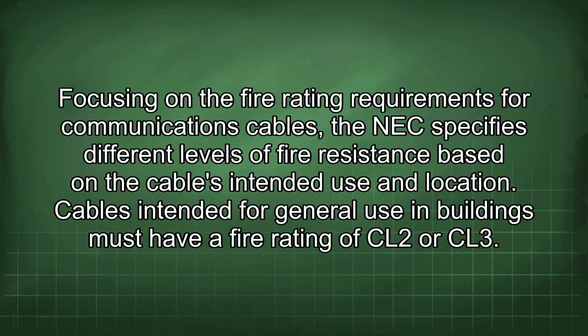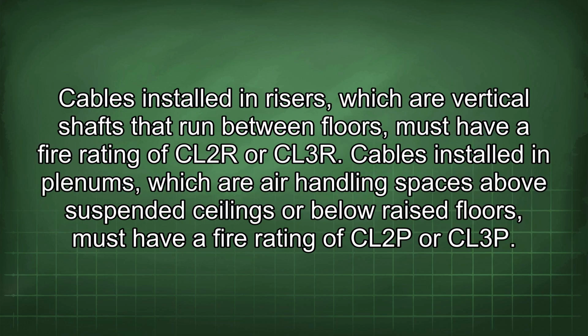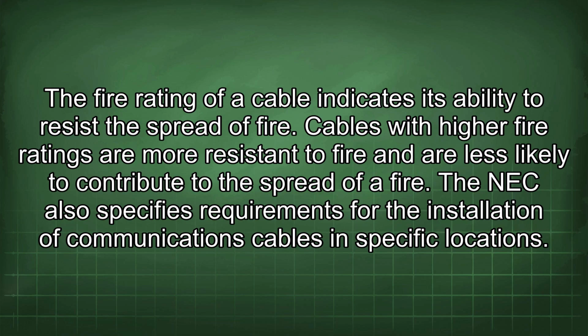Focusing on the fire rating requirements for communications cables, the NEC specifies different levels of fire resistance based on the cable's intended use and location. Cables intended for general use in buildings must have a fire rating of CL2 or CL3. Cables installed in risers, which are vertical shafts that run between floors, must have a fire rating of CL2R or CL3R. Cables installed in plenums, which are air handling spaces above suspended ceilings or below raised floors, must have a fire rating of CL2P or CL3P. The fire rating of a cable indicates its ability to resist the spread of fire. Cables with higher fire ratings are more resistant to fire and are less likely to contribute to the spread of a fire.